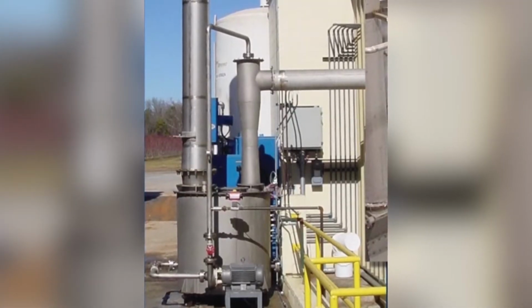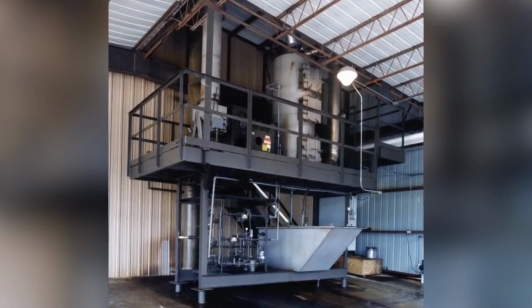to remove vapors, gases, and particulates generated by the exhaust of some process equipment. Wet scrubbers are often located downstream from furnaces, dryers, mixers, bagging stations, and other emission points. They're often the best option for applications where the particulate being collected is combustible. Using water to scrub particulate from an airstream eliminates the dust's explosion potential.